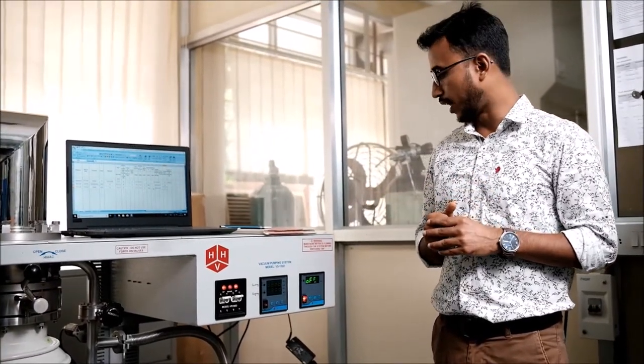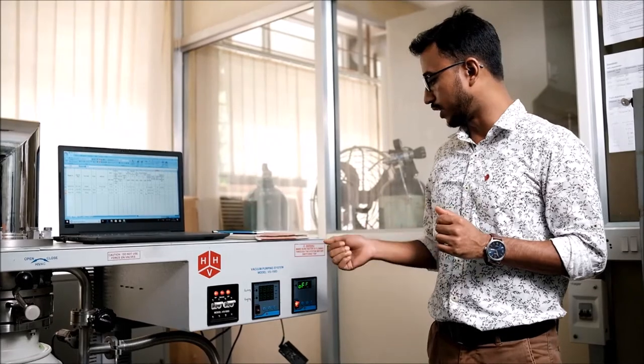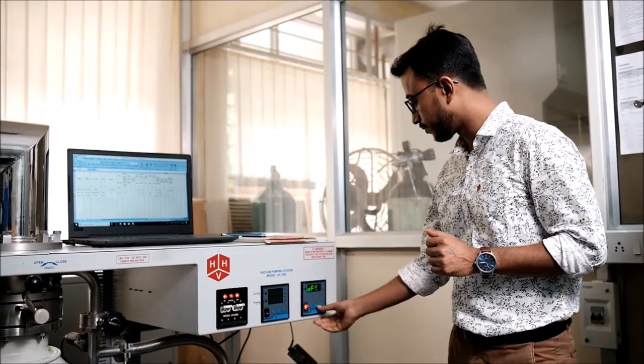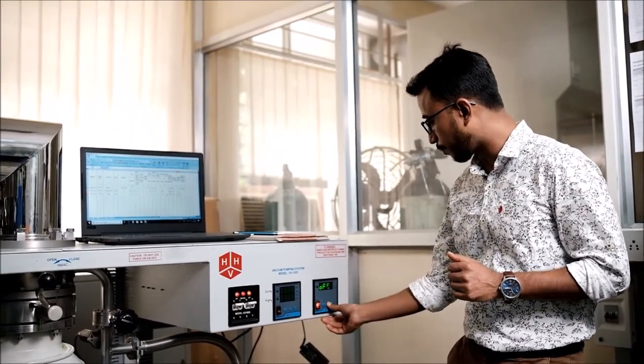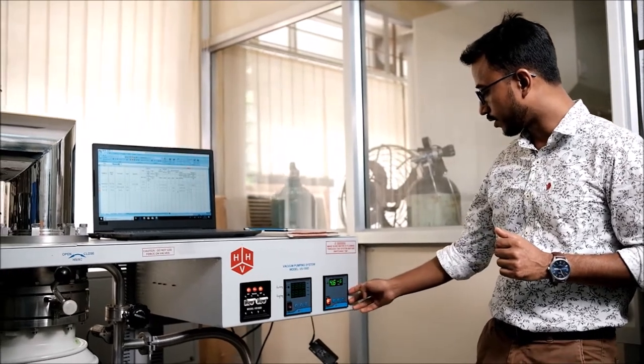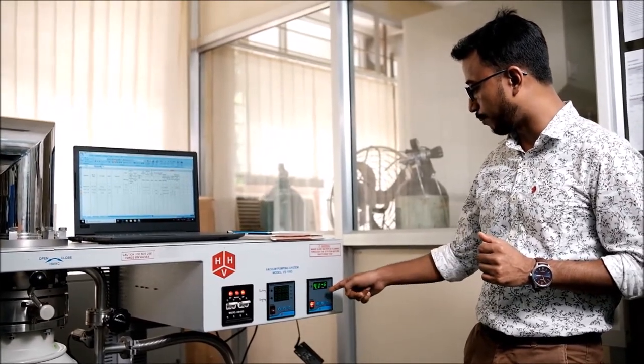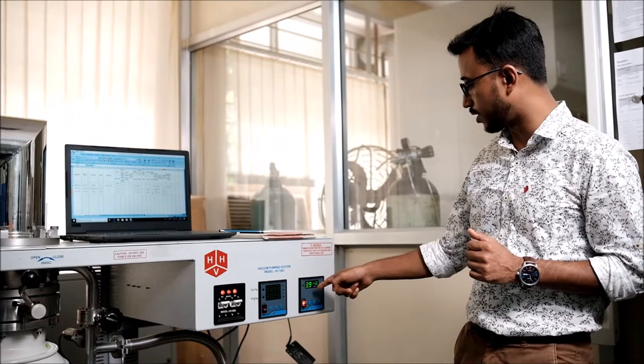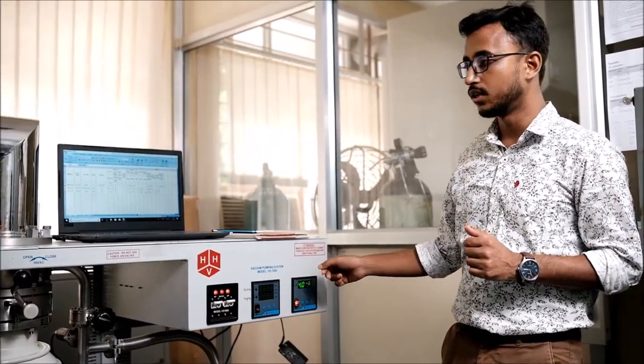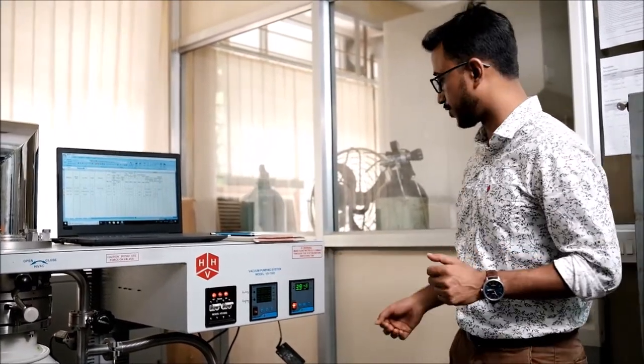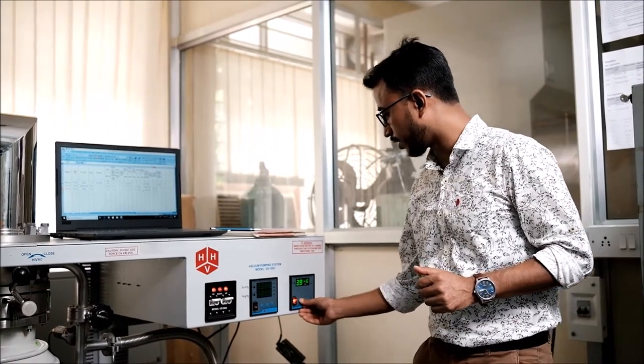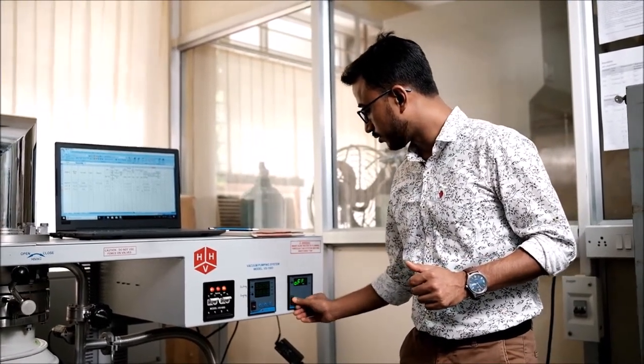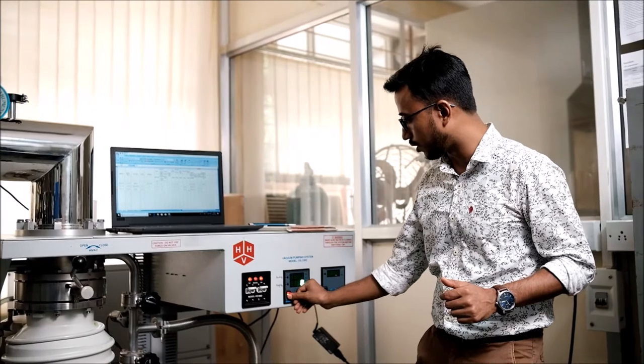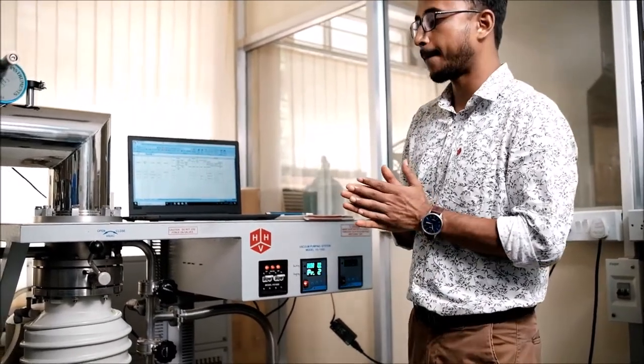Now we are back after an hour break, and now we have to check what pressure has been reached. So we will switch on the Penning gauge, and we see the pressure is below 4.0 to the power minus 6. So now we can start our deposition. So we switch off the Penning gauge and turn on the Pirani gauge to see the pressure.